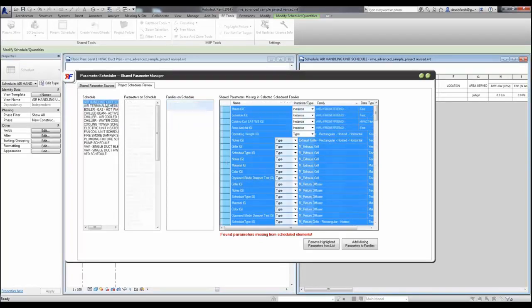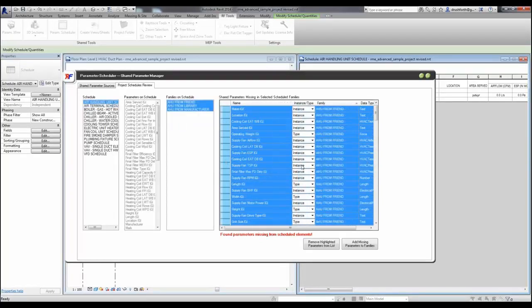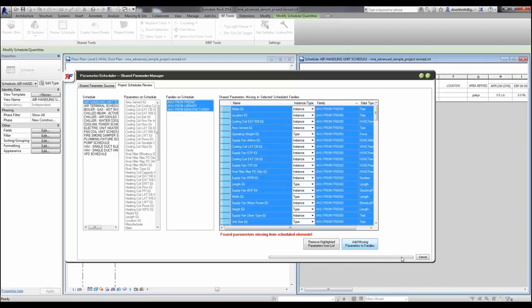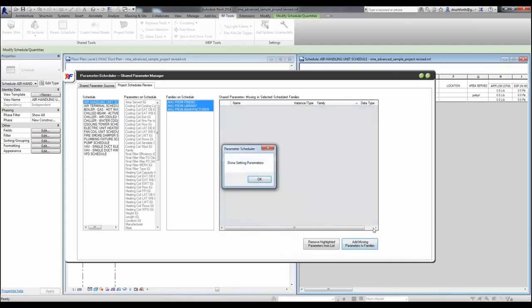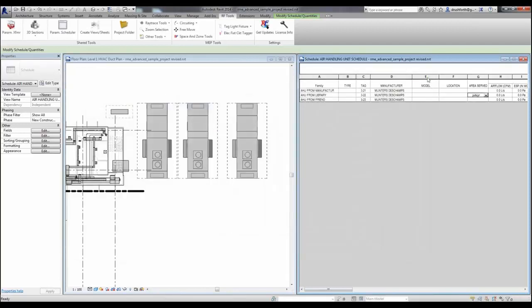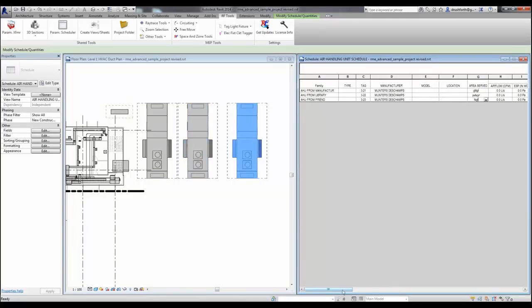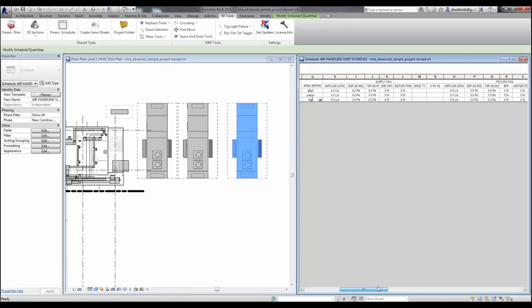So back to the air handling unit schedule, all I have to do is click add missing parameters to families, and it will automatically process the families in my project and add any missing parameters that are found. I can do this for one or multiple families at a time. So back here in the project, I can now type in whatever data I want into these schedules that were previously not editable.